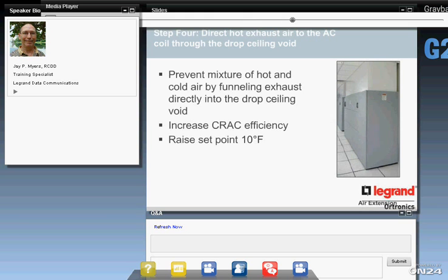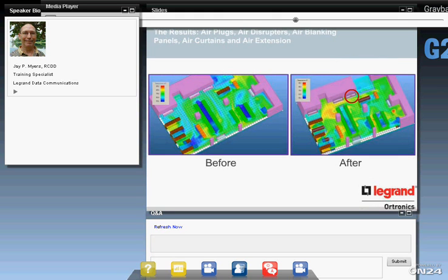Now, so far, all we've done is improve the cooling. But where you start to save the money is when you start edging up your set points. And this allows us to edge those up and still have acceptable temperatures for our equipment. So here's before and after. Now on the right-hand side, you can see that red circle there. We've turned off one CRAC unit. Those cold aisles are now in perfectly good temperatures, but they're not being excessively cooled.